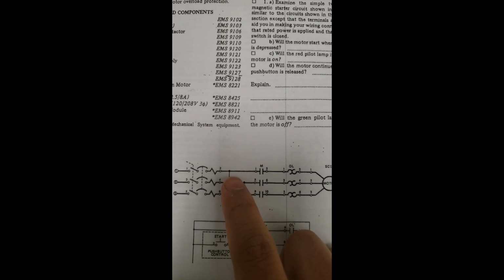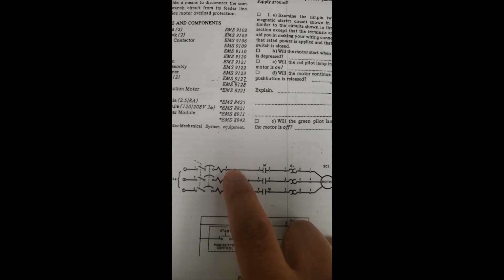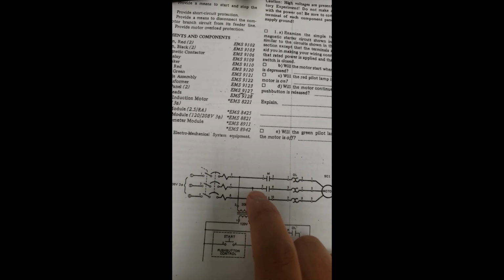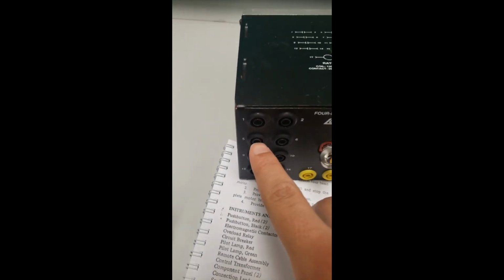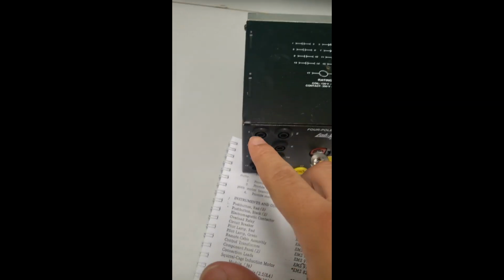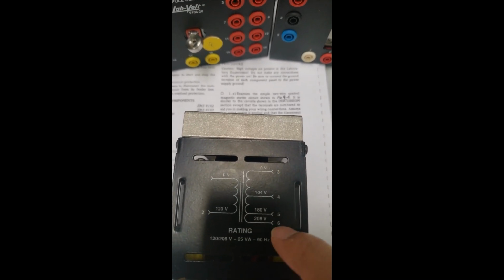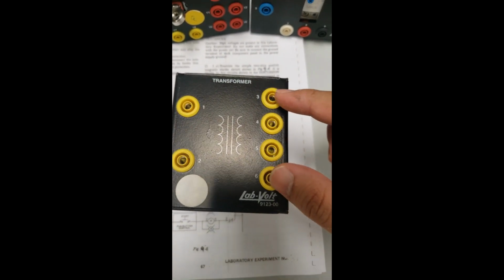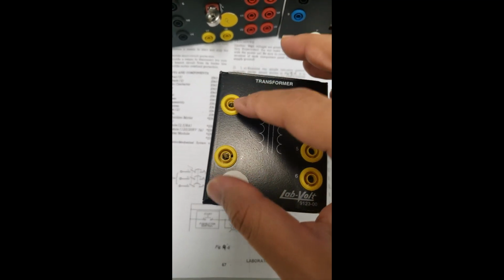The control circuit. In the control circuit, I have to take 2 wires from the wire that is connecting 2 of the circuit breaker and 1 of the contactor. So I'll take from 1 and 5 of the contactor to a transformer 3 and 6, which has a rating of 208. So I will connect 1 and 5 to 3 and 6 because the total is 208. The 2 wires will come here, 3 and 6, and it will go out from 1 and 2.